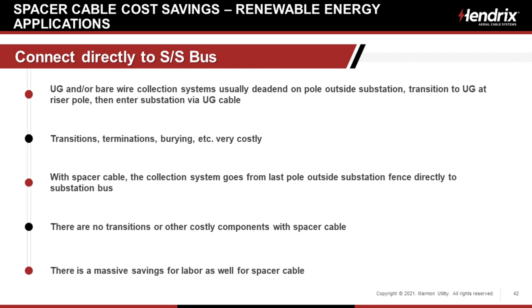I said we can connect directly to the substation bus. So underground and bare wire collection systems usually dead end on poles outside the sub, transition to underground at the riser pole and through the substation via an underground cable. These transitions, terminations, dead end poles, burying, boring, etc., are very costly. But with spacer cable, that collection system goes from the last pole outside the sub directly to the bus. There's no transitions or other costly components.